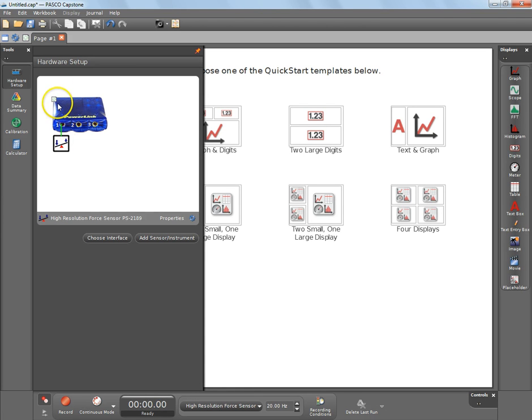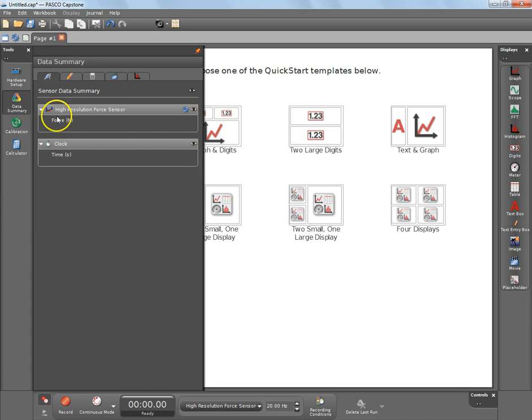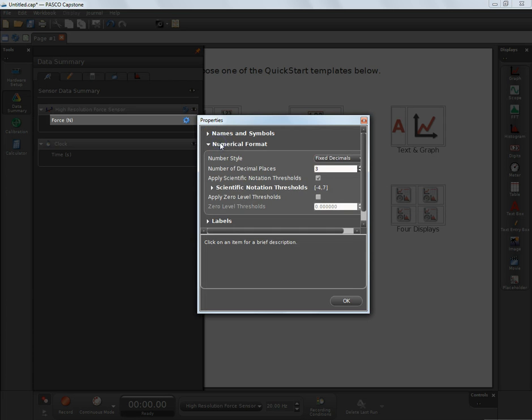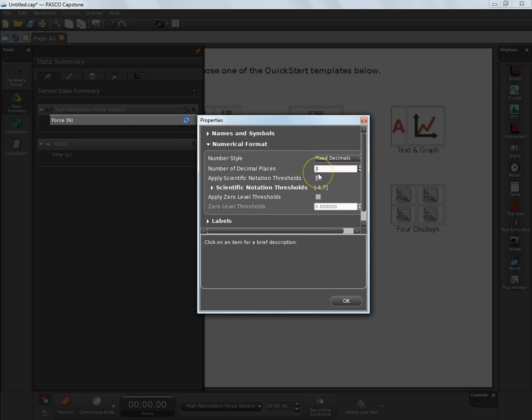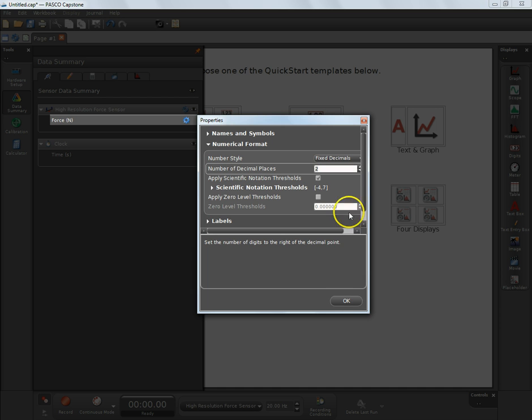If there is a caution sign it could be the power is not on or the plug is not all the way in or the USB cord is not all the way in. Those are things that can be checked. The data summary here is for force and the machine itself is rated to three places after the decimal. It's probably not going to work to three places after decimal for us because we're going to have a little bit of motion in it, we're going to have a little bit of water in it and stuff. More realistically two places after the decimal is more realistic for this lab.